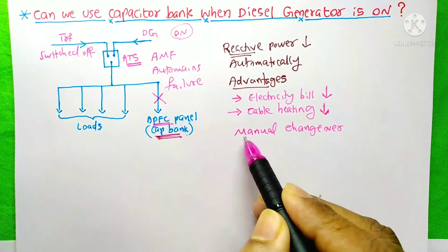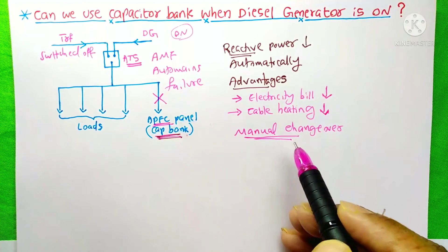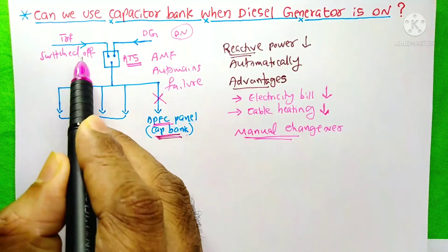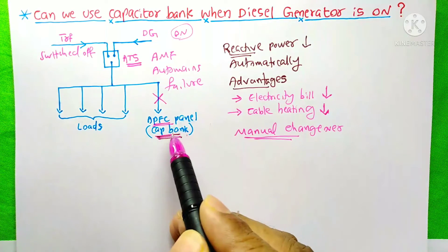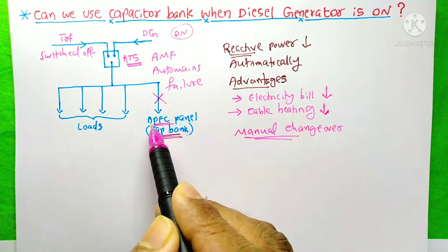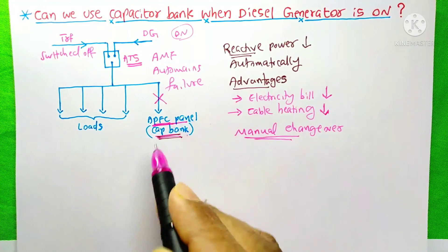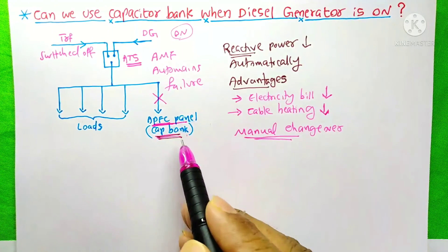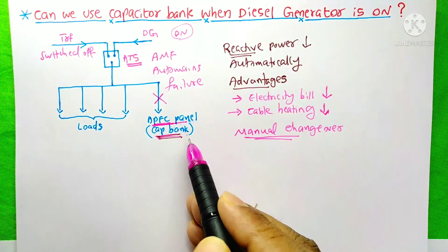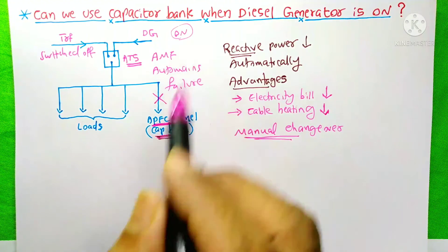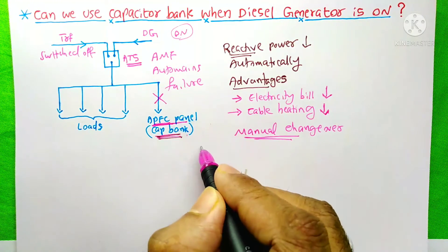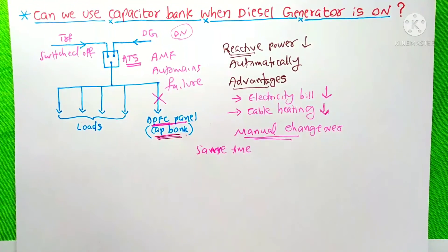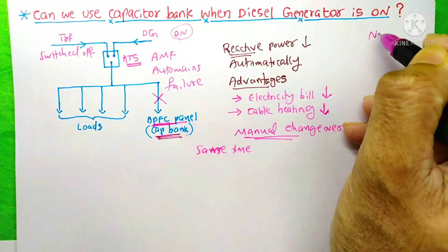If we have a manual changeover switch, then at any point the capacitor bank should be switched off before the DG is turned on. That means both the capacitor bank and the DG should not be on at the same time. So I hope you have understood this topic, and the answer to this question is NO.